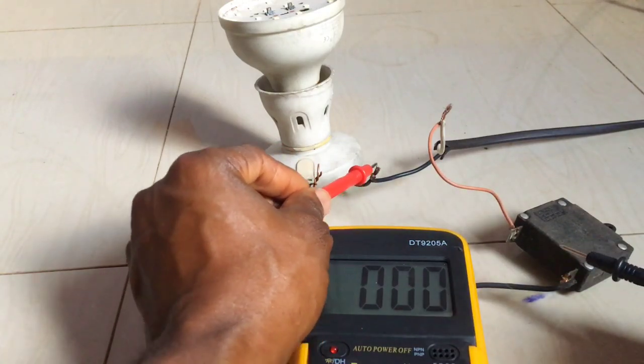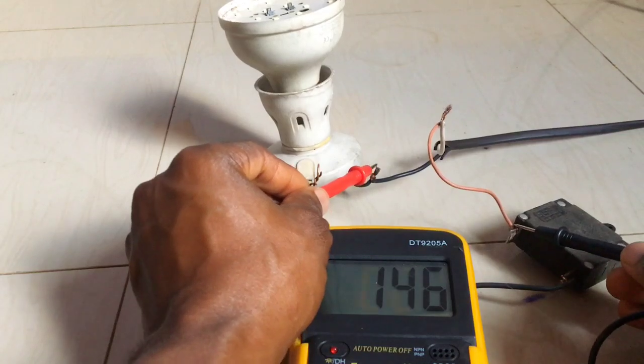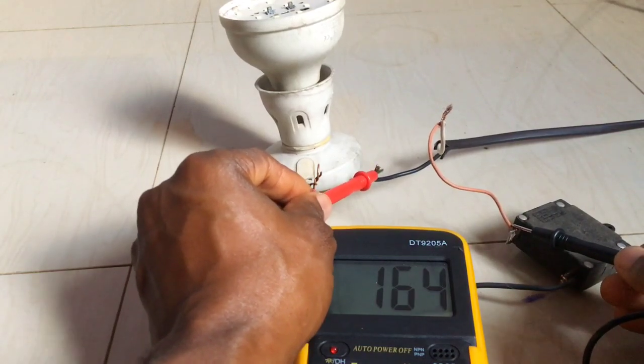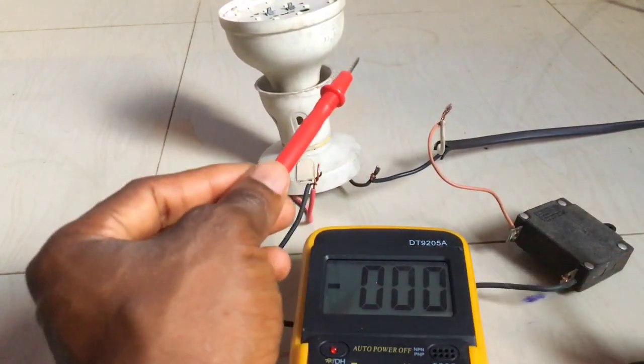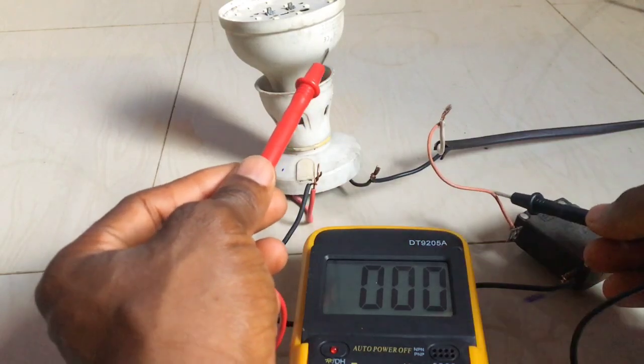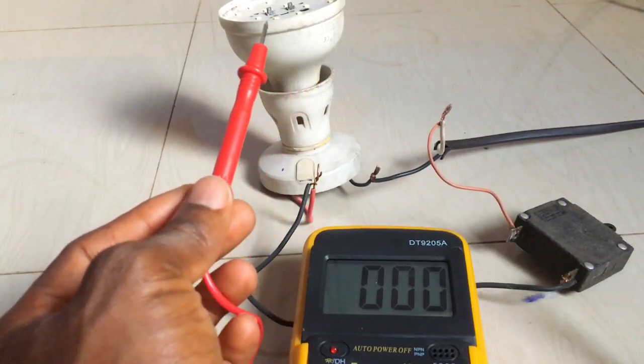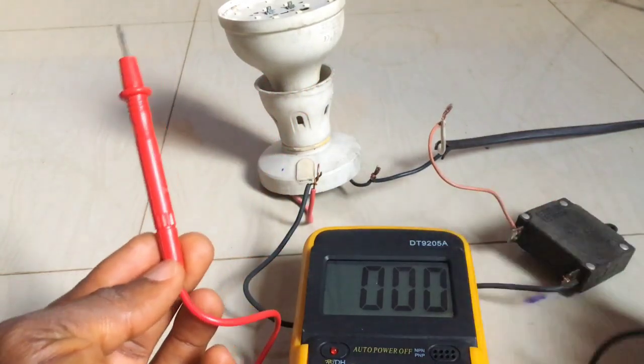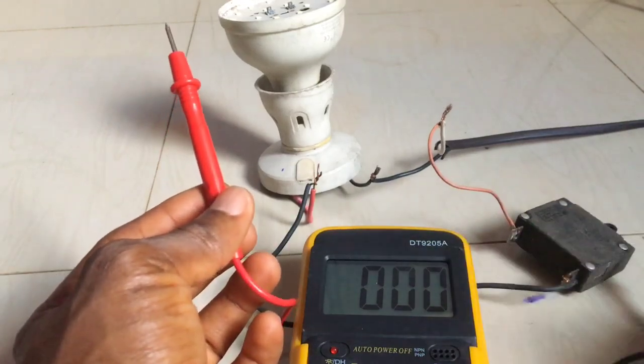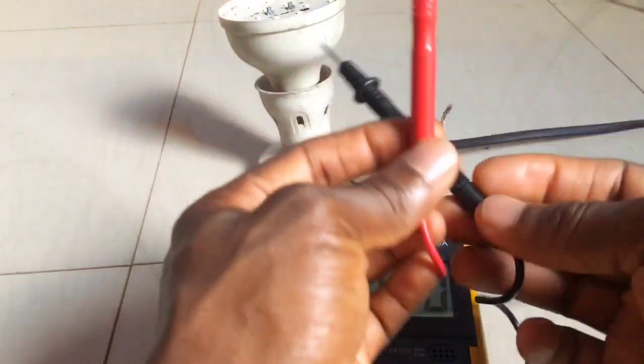So let's see. Good. So we still have about 160-something volts AC, which means this red line coming from the distribution board, the circuit breakers of the distribution board, is energized. Okay, so if it is energized and when your switch is on your light still doesn't turn on, then you replace the switch. It's as simple as that.